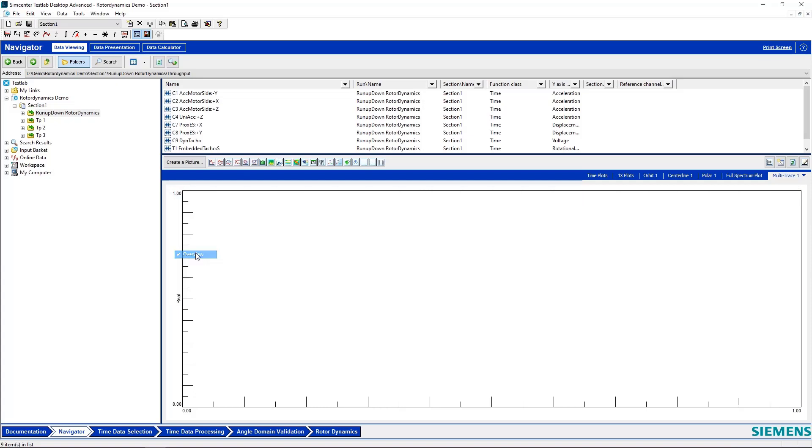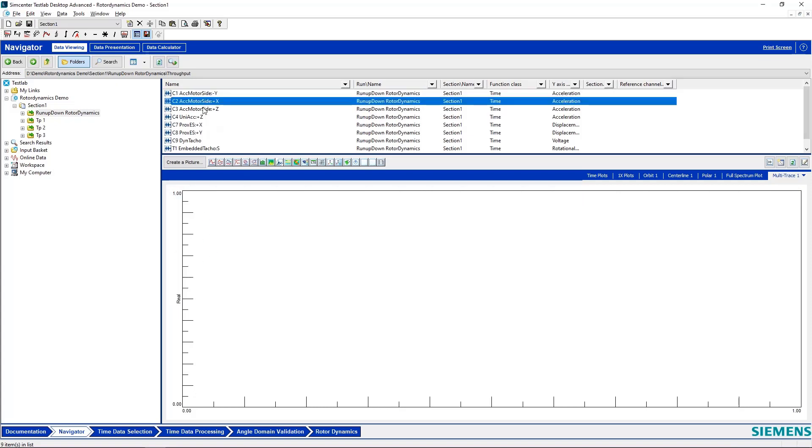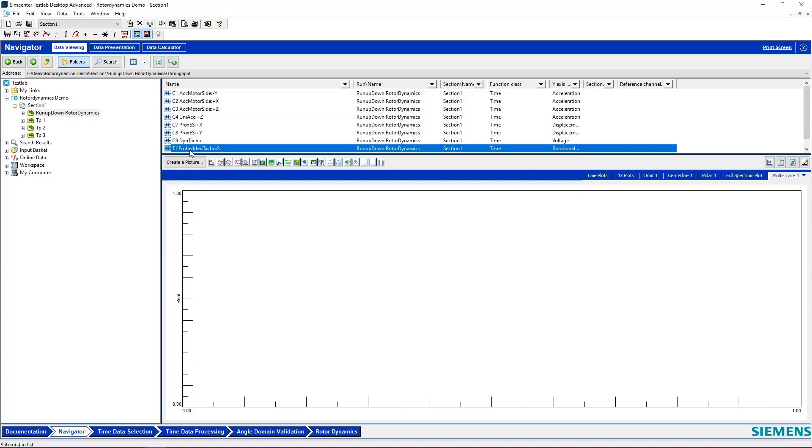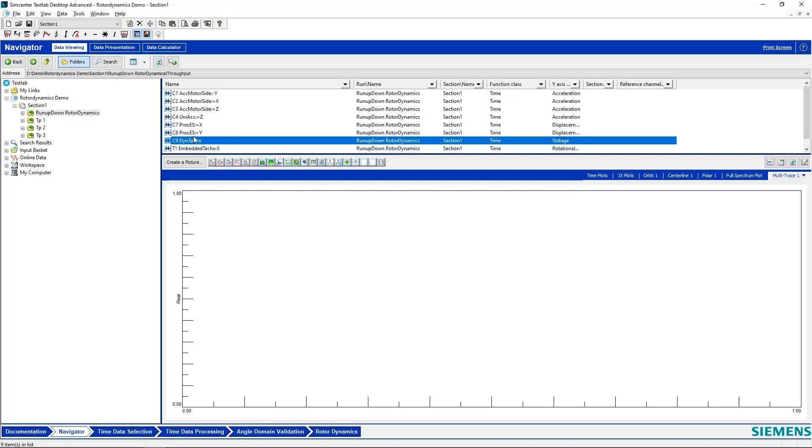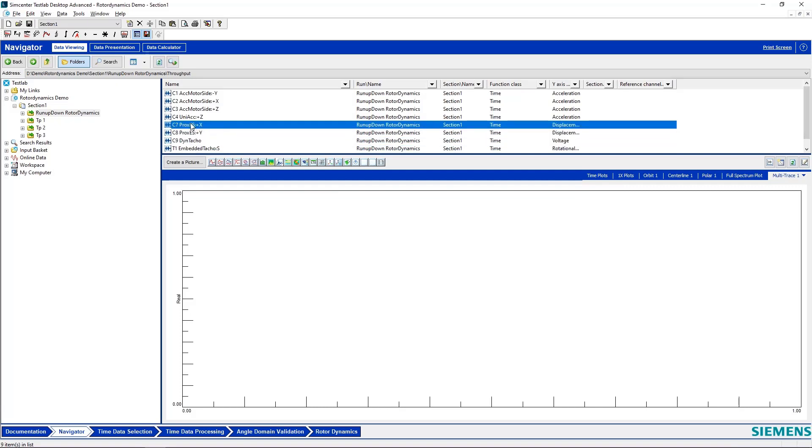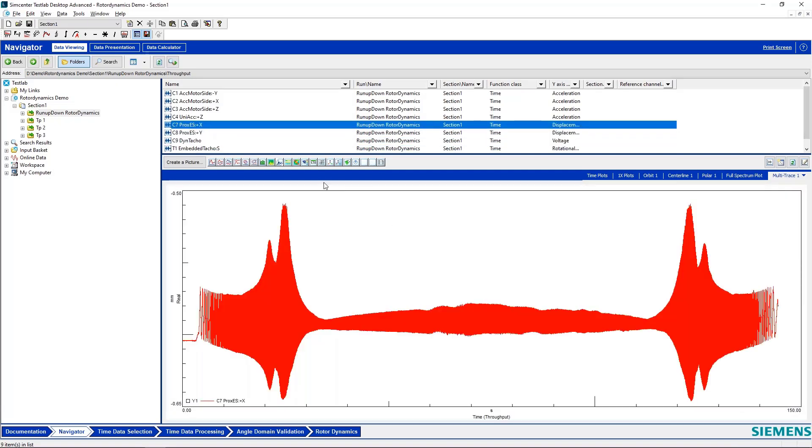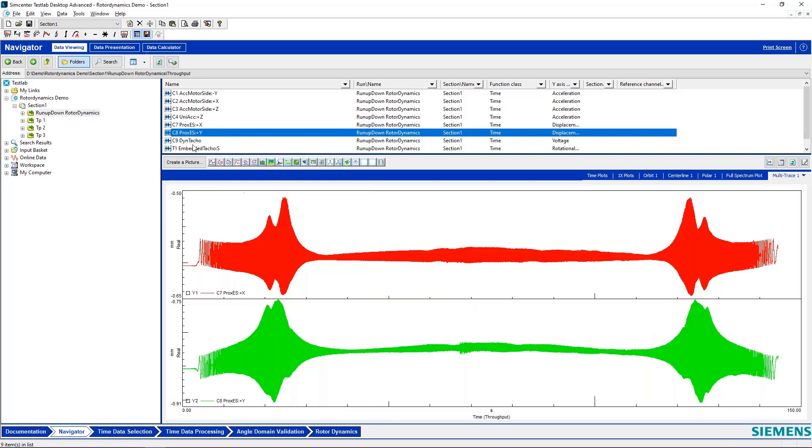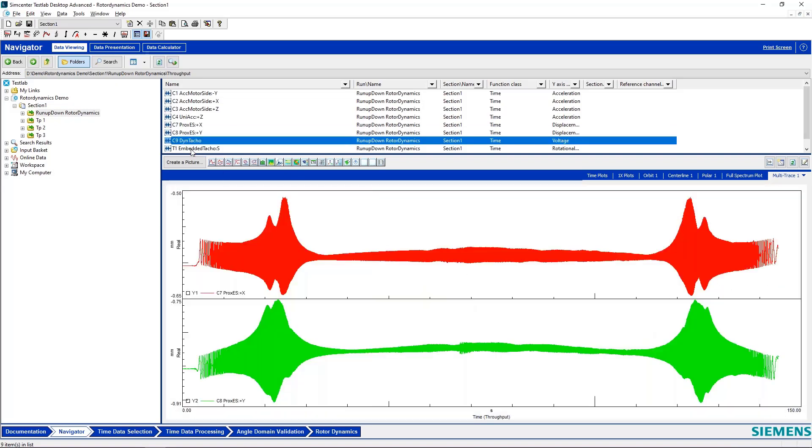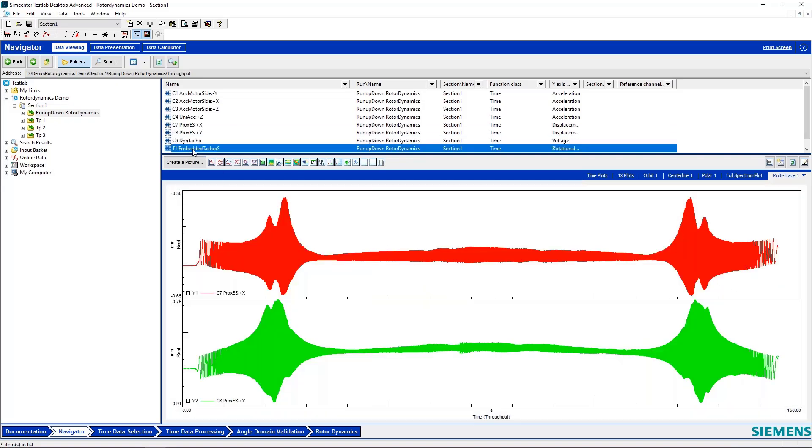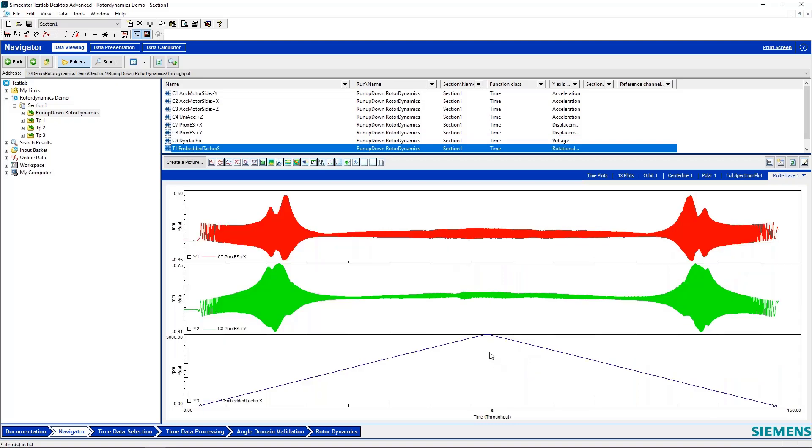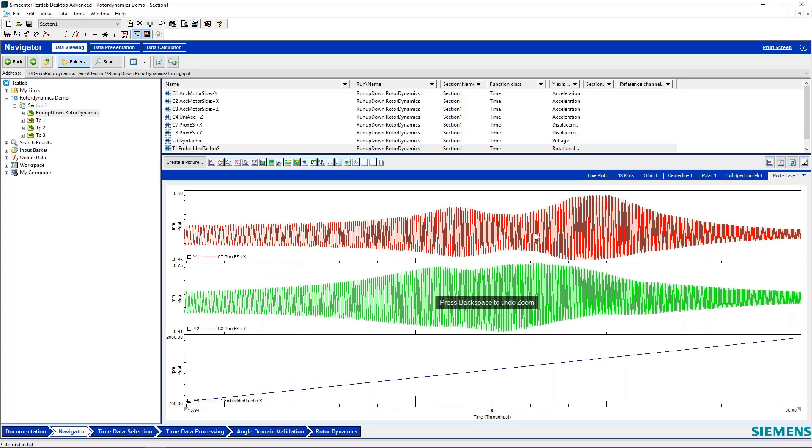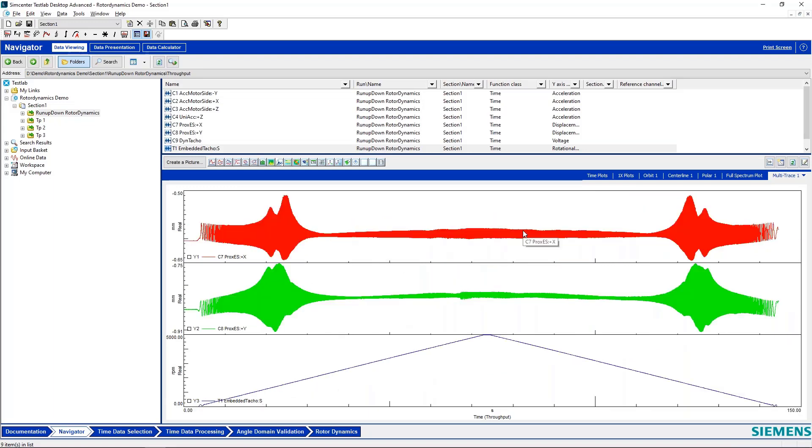So I've got some accelerometers and then I have two proximity probes and a key phasor sensor. I'll show you my displacement sensors and then I'll show you my tach or key phasor channel. So I've got some data where I've done a run-up and a coast-down. You can see during the run-up I get these higher levels of vibration on my displacement probes, which probably indicates that we're passing through a resonance of this particular machine.